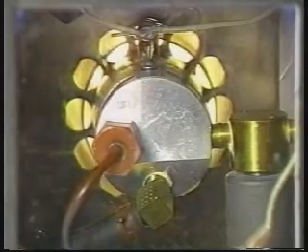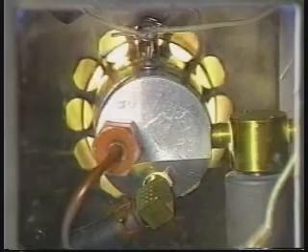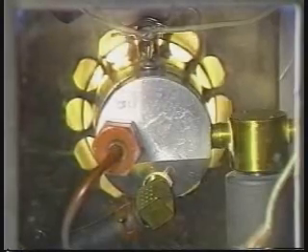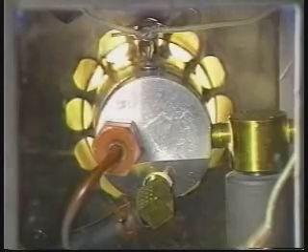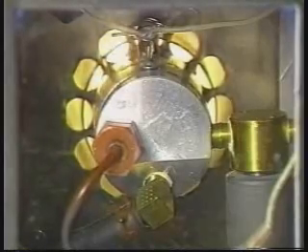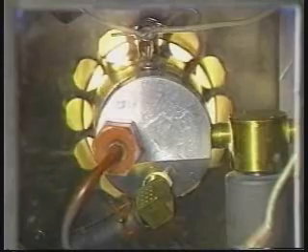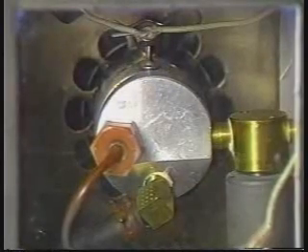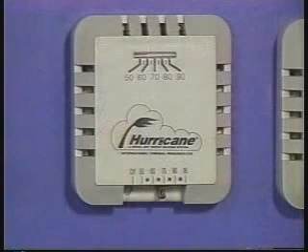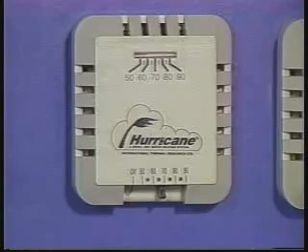The igniter remains on for another 20 seconds. The burn is now self-sustaining. The color of the flame should be a bright yellow. The flame remains on until the thermostat is satisfied or until the fluid temperature in the boiler reaches 180 degrees, at which time the operating aquastat will open and the flame will go out. As long as the thermostat continues to call for heat, the furnace will continue to cycle on the operating aquastat.